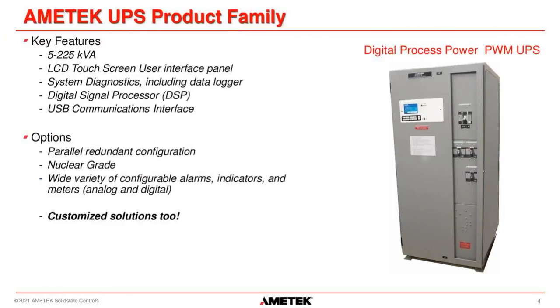And the AMETEK SCI UPS product family, the key features: we do UPSs that range in size from 5 to 225 kVA, single phase and three phase. We have an LCD touchscreen user interface panel, what we call our MIMIC panel. We have system diagnostics, which include a data logger. So we log all of the alarms and data within our system. We have digital signal processors and a USB communications interface.